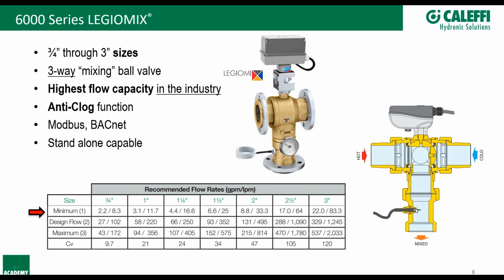So you obviously chose, or Caleffi chose, to go with a ball valve style, whereas a lot of the competition is using, I believe, a globe valve. Could you go into the benefits of the ball valve style? Ball valves, traditionally, are not the best way of controlling flow, but temperature in this case is definitely something we can do. Globe valves might have a little more definition in their stroke, but our valve, as well as anybody else's globe valve, are both listed to the same standard, ASSE 1017, which ensures the accuracy of the valve, plus or minus a few degrees at whatever flow rate. So everything we offer is listed to ASSE 1017, so it's going to be just as accurate as the next guy per the standard, and it's going to do just great.